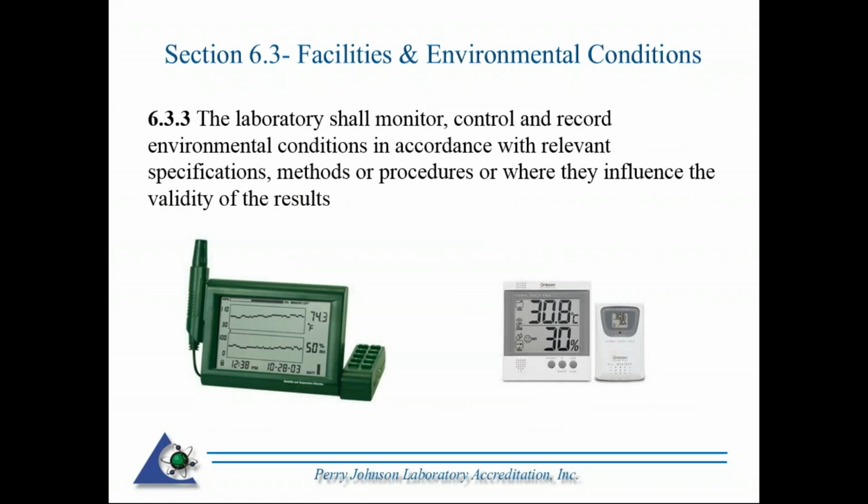Along with that, the laboratory shall monitor, control, and record environmental conditions in accordance with the relevant specifications, methods, or procedures, or where they influence the validity of the results. So if you have those conditions specified and documented, they need to be monitored, such as depicted here by perhaps a data logger, or captured in real time with a temperature and humidity type device, if those environmental conditions are important to the activity being undertaken. Nothing new here. That's always been required in the 2005 standard.